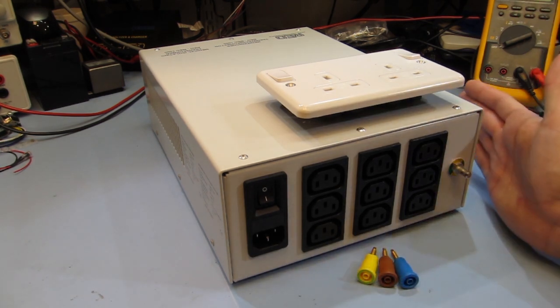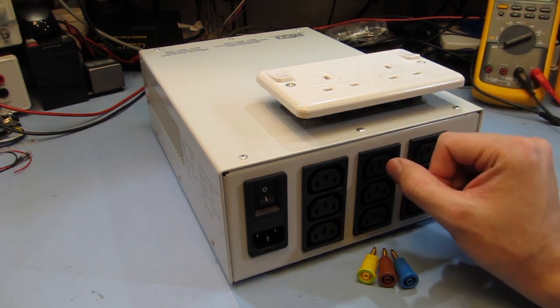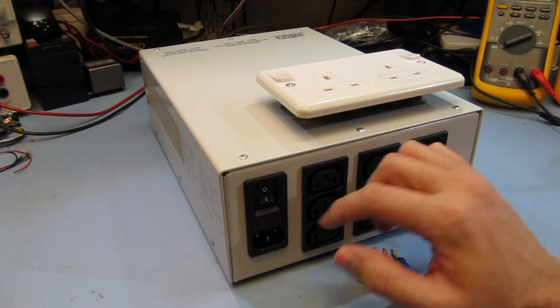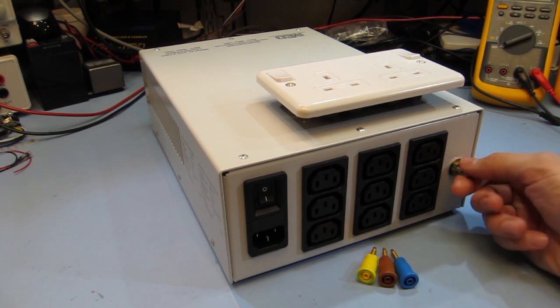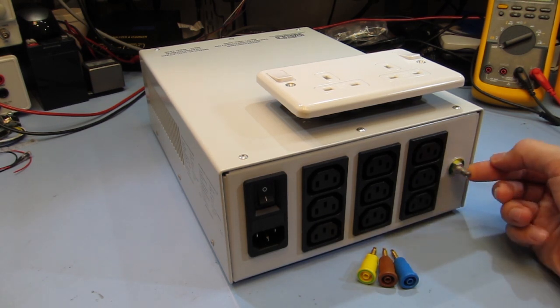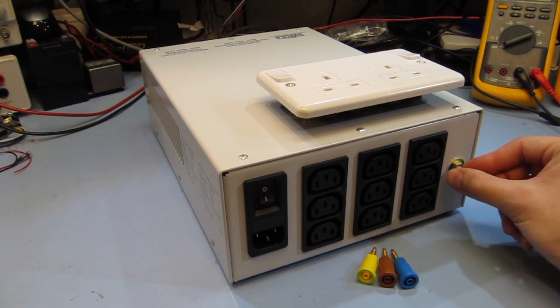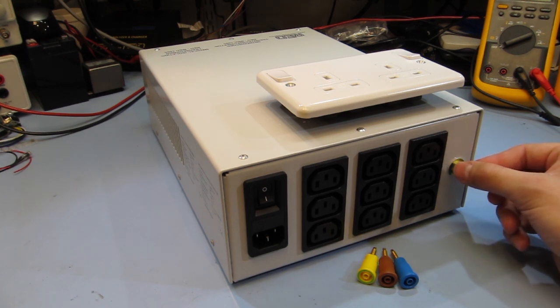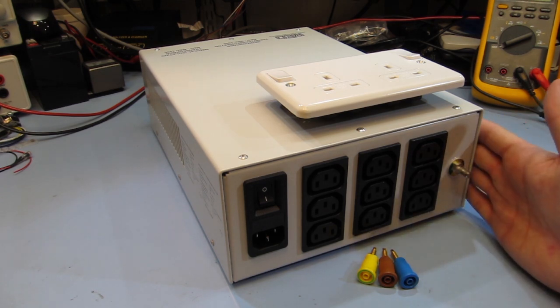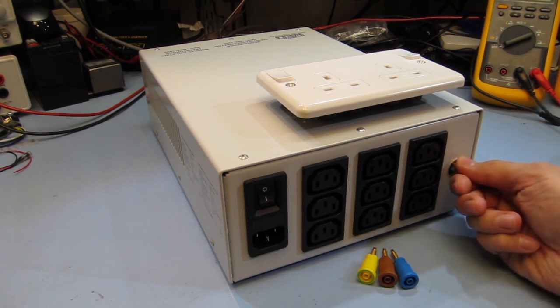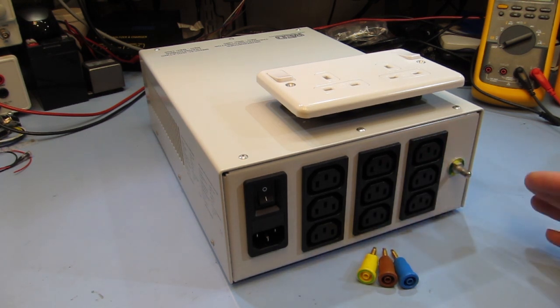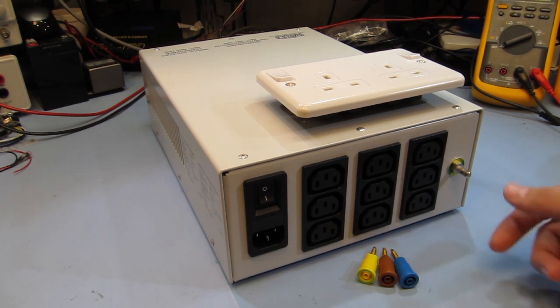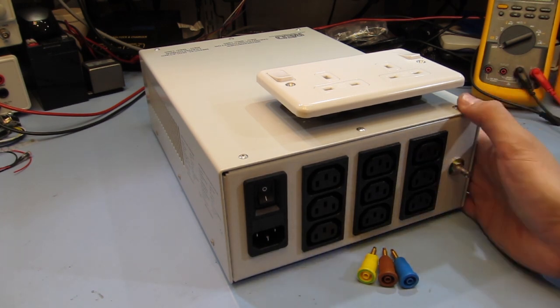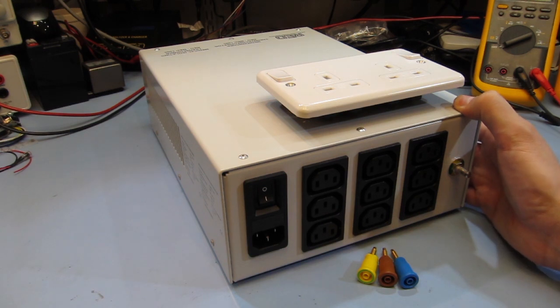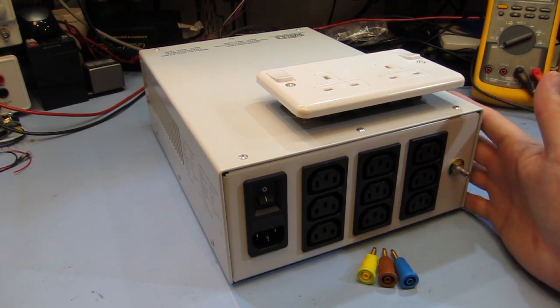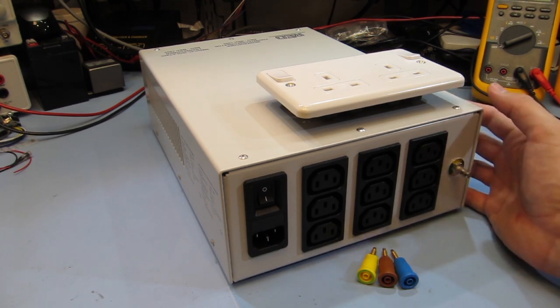So the other minor annoyance with this transformer for my purposes is that the earth pin of these connectors is permanently connected to mains earth, and also to this earth stud here. On medical devices these earth studs are pretty common, the reason being that you want to minimise the potential between electronic equipment. So they have an earth stud on all the devices and an equipotential earthing bar in, say, the operating room, and you connect all the devices together. Then if you're touching two different devices there's a very low risk of any touch potentials between the devices, which could lead to high leakage currents through the patient.